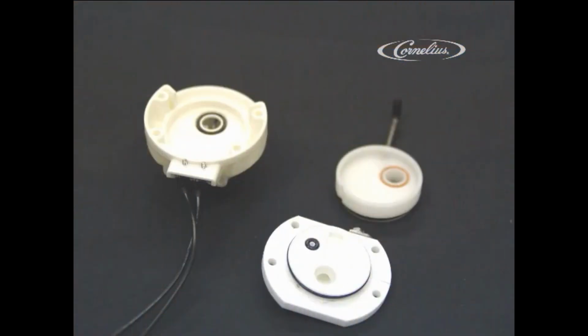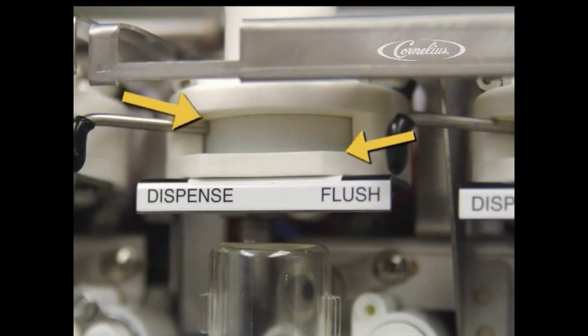There is a series of O-rings that make up the bottle adapter assembly. It is key to the proper operation of this assembly that these O-rings are properly lubricated and remain in the correct positions. The adapter has 3 parts: the top, the slide or lollipop, and the bottom. Worn or dried out O-rings will show in a couple of ways. If these larger O-rings are worn, you will start to see traces of concentrate between the sections. This is very pronounced with your thinner concentrates such as cranberry or fruit punch.